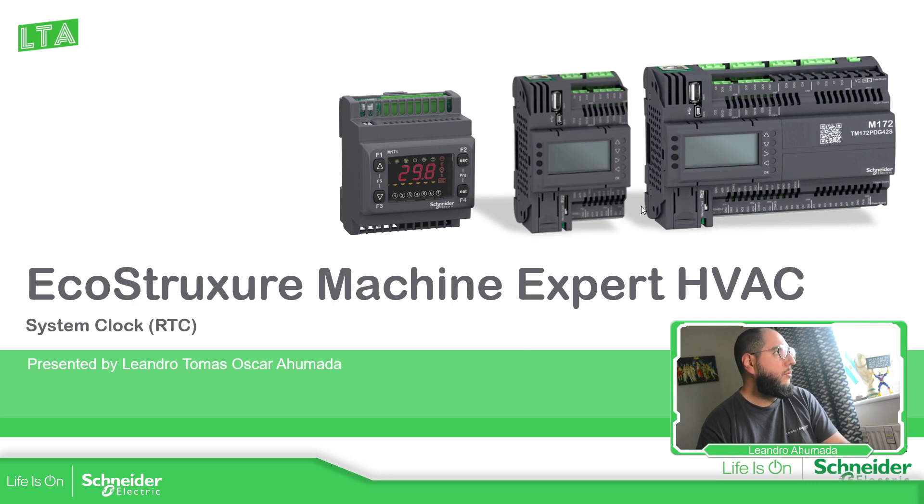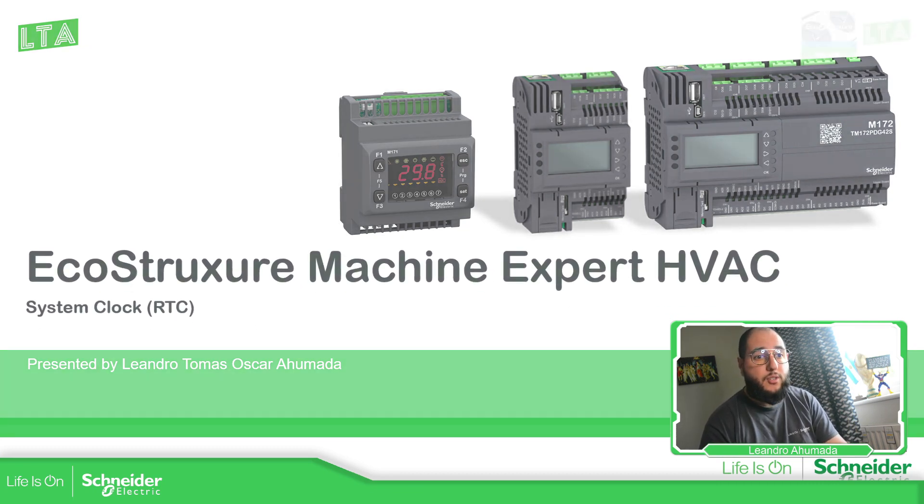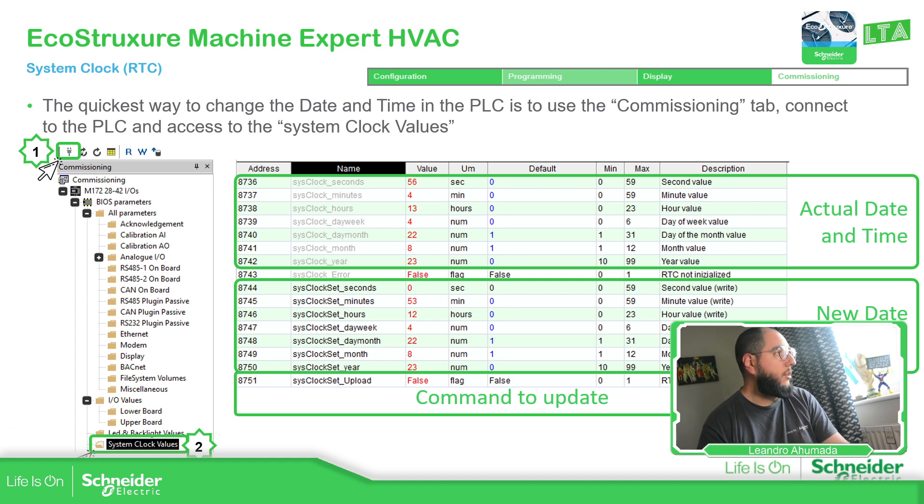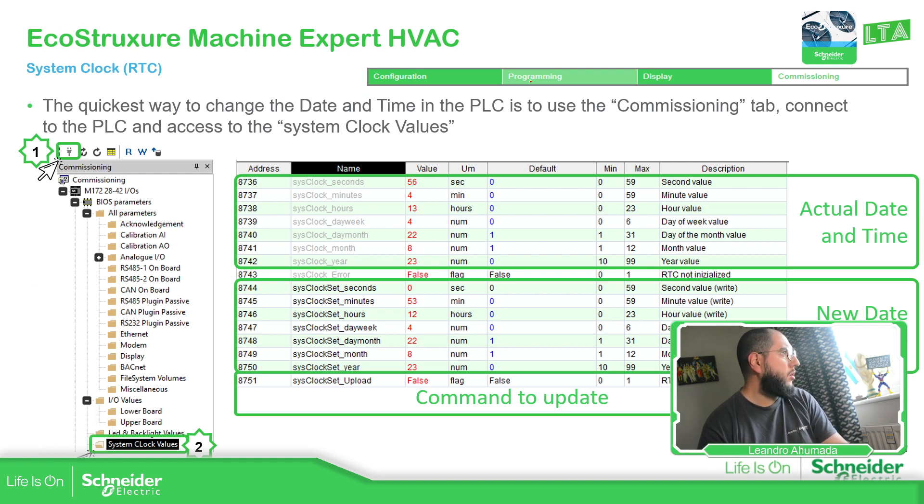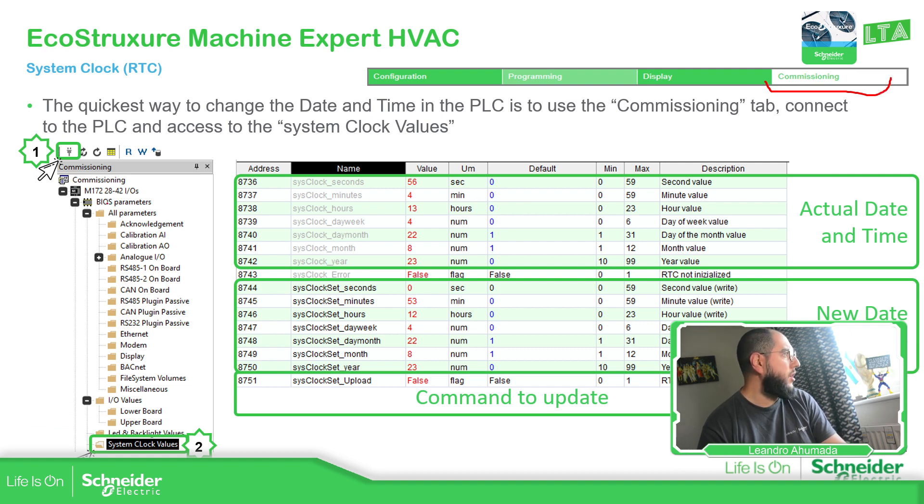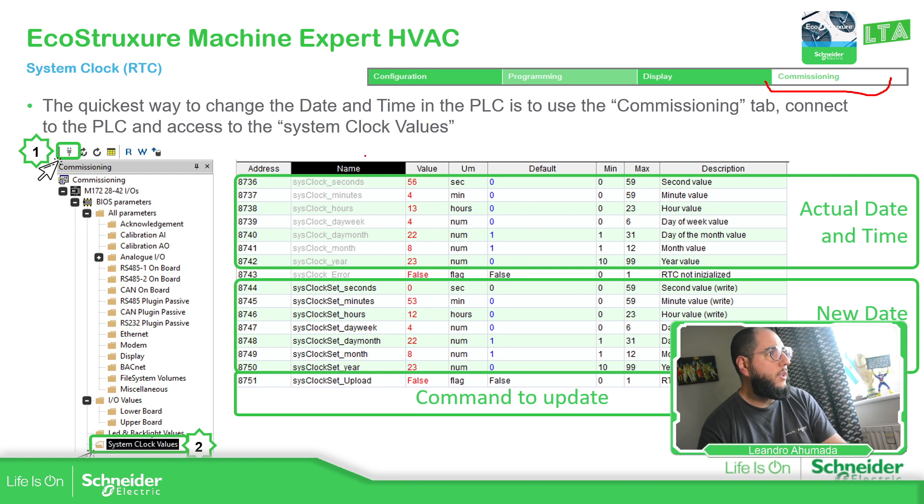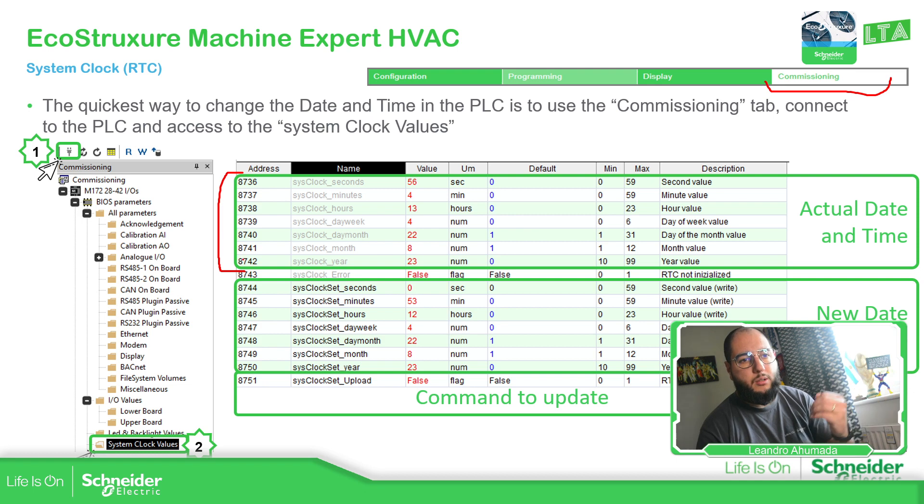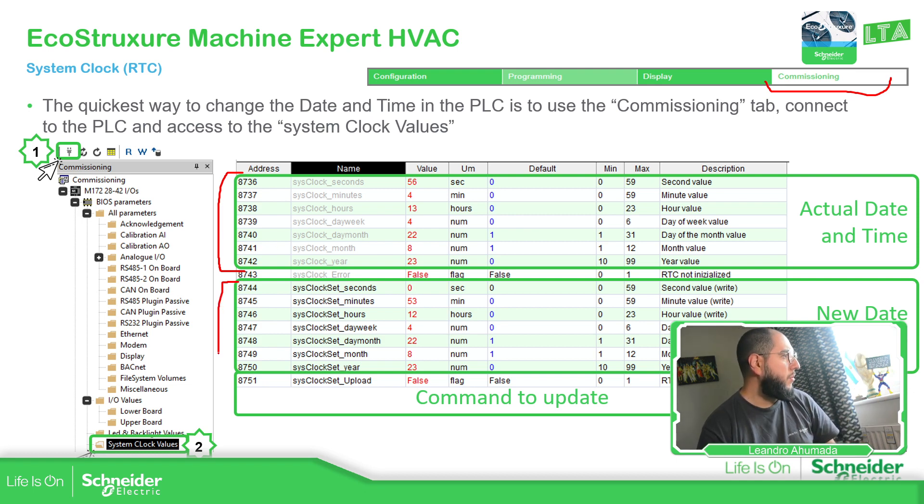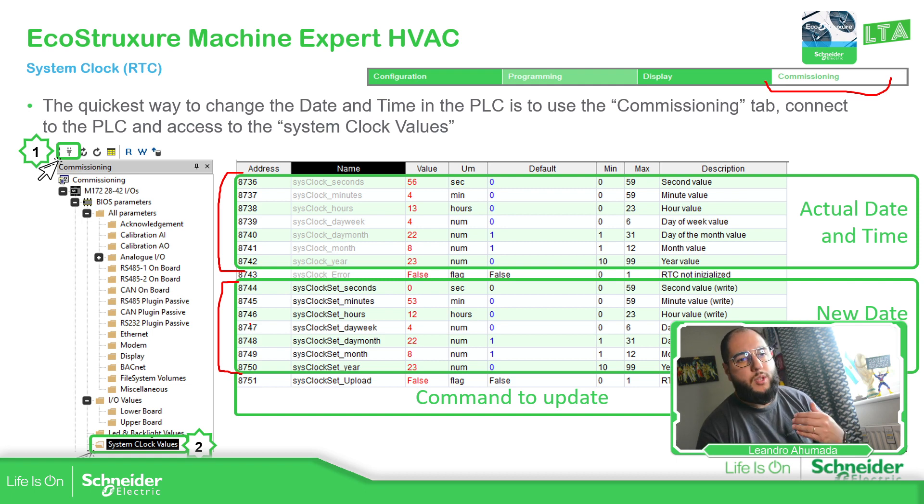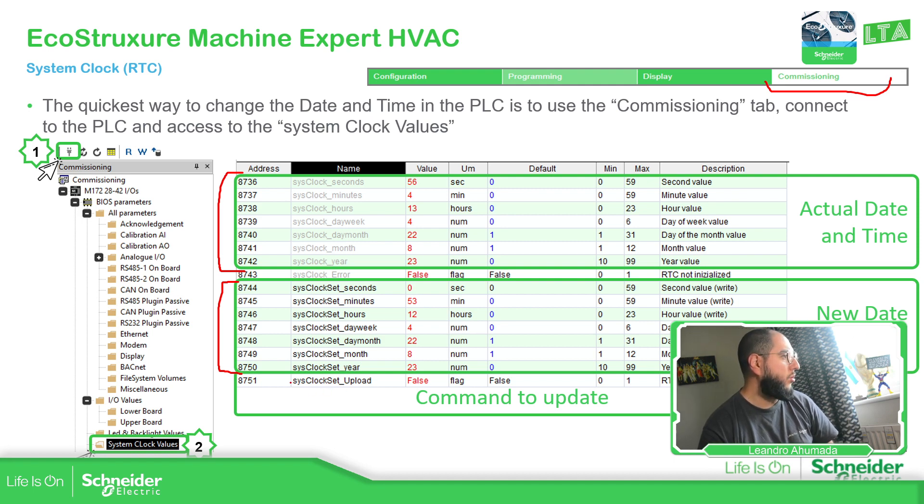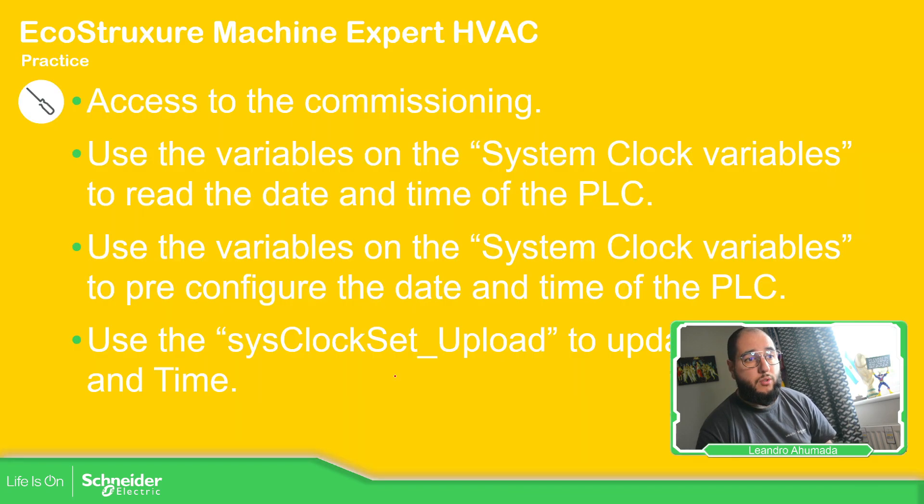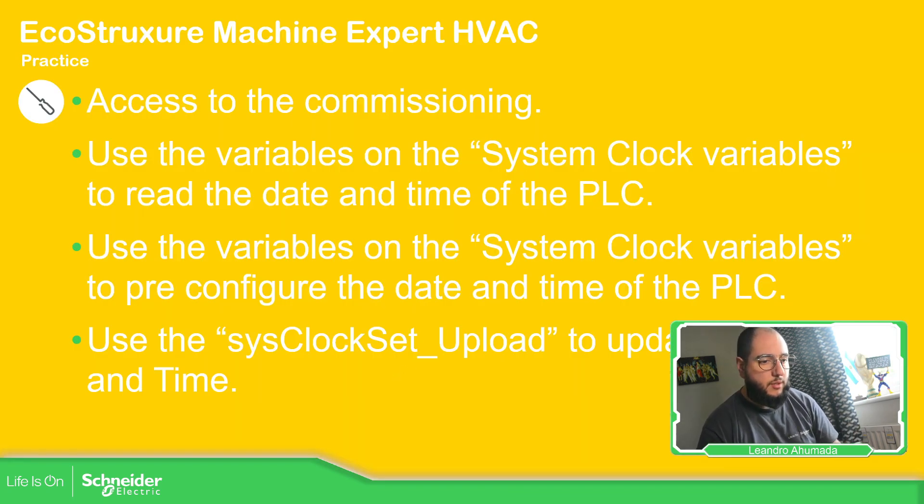So the M172 has the real-time clock and we have the possibility to change that, change the actual date and time. So the easiest way is to go to commissioning, just put here, go to the commissioning tab, and then go to the system clock values folder. In there you have one set of variables to see which is the actual date and time, and then another set of variables that are related to the new date and time that we want.